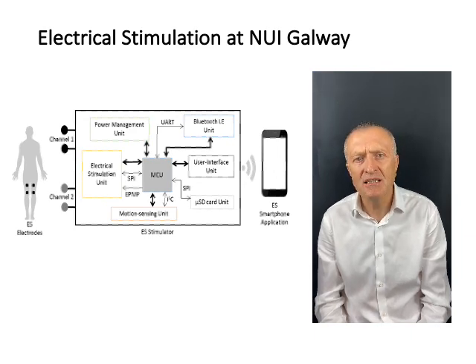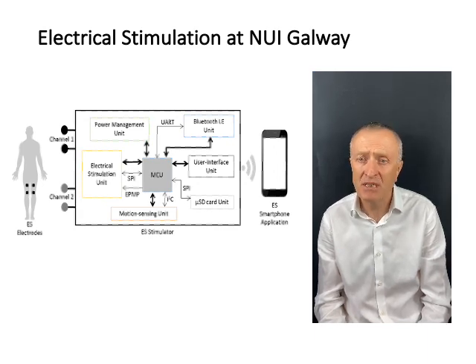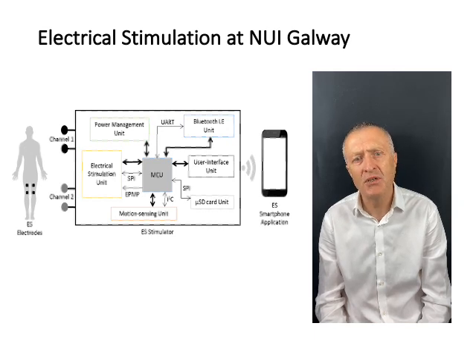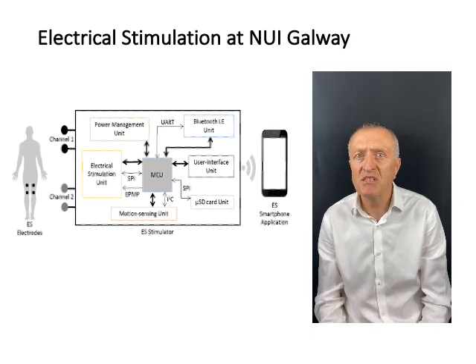The MCU reads these signals to understand the movement patterns of the wearer and thus decide to deliver stimulus using the electrical stimulation unit, which has two stimulation channels which connect to the user using skin surface electrodes. Data from the sensors can also be stored on the SD memory card on the micro SD card unit. The stimulator communicates with a smartphone using the Bluetooth low energy unit, and the user can configure the stimulator for their unique needs using their smartphone and a specially designed app. Then importantly, the whole unit is powered using the power management unit and a rechargeable battery.